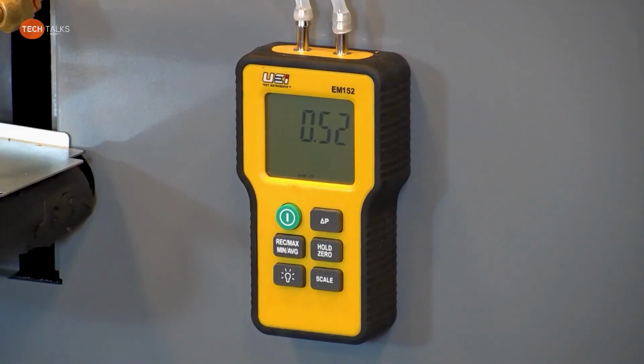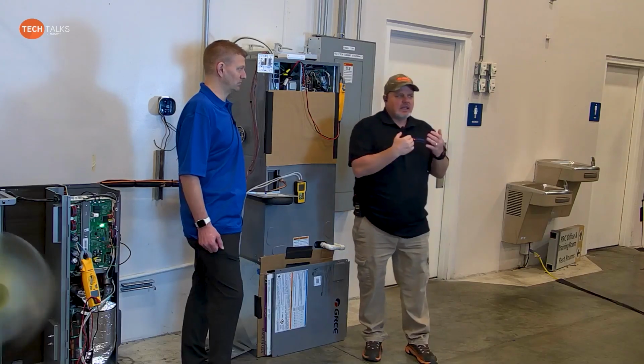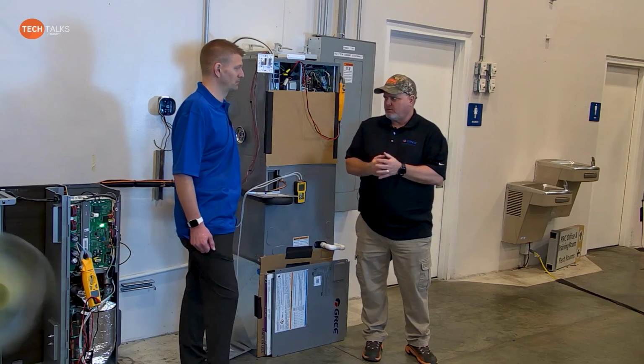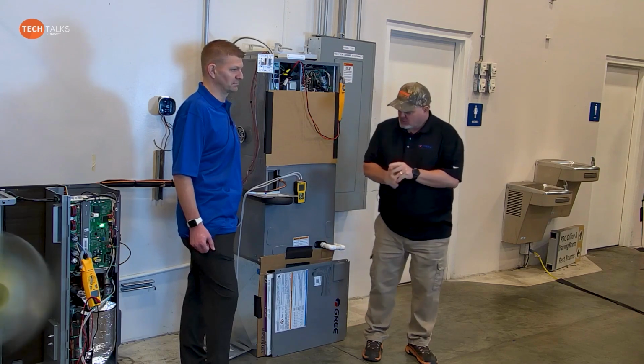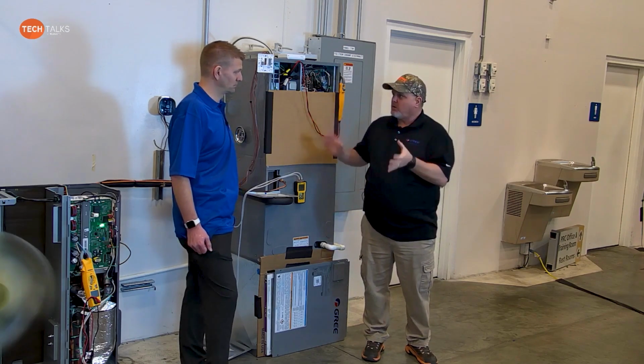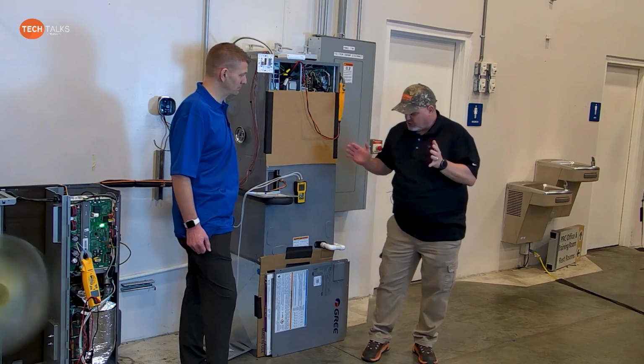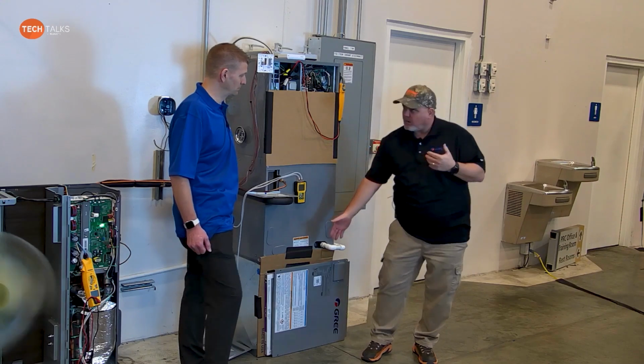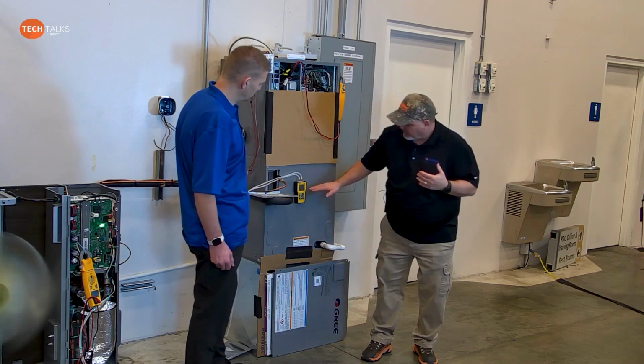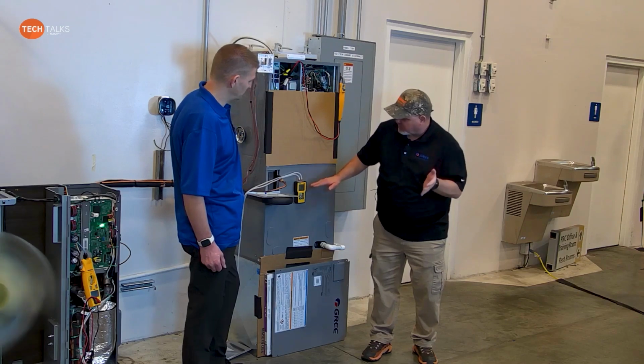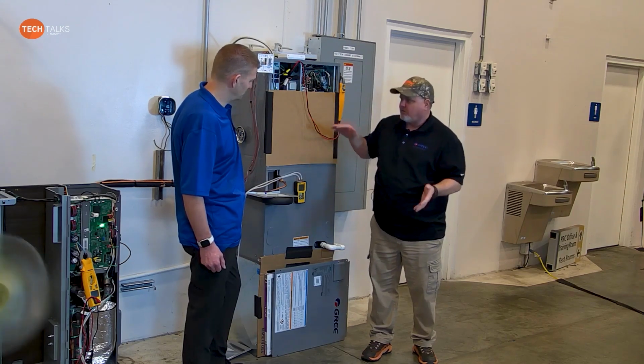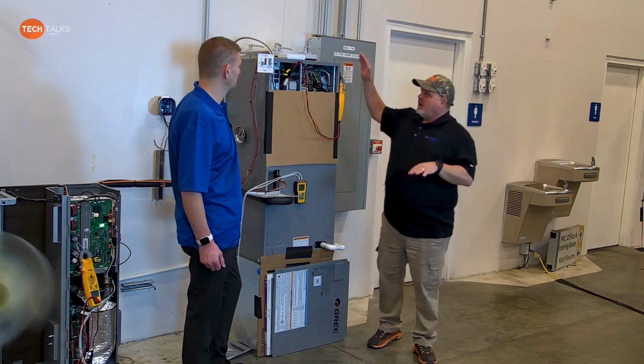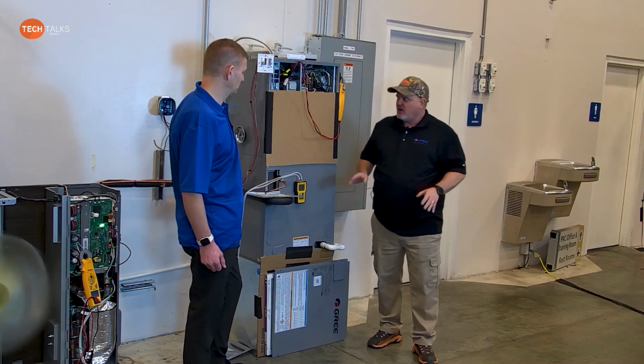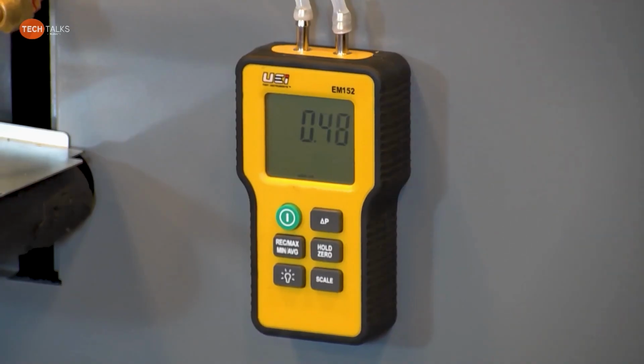So now look at my static. I'm up at 0.5. Now, you have a fixed torque motor. I chose level 3 as my airflow, okay? Let's mark where we're at right now. This is a good demonstration, so I know where I'm at. I'm running a 0.48, that's fluctuating, 0.46, 0.48, up to 0.5, right around in there, okay? I'm not going to change anything other than, JD, let's lose the call. All right.